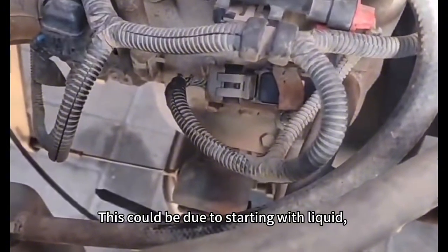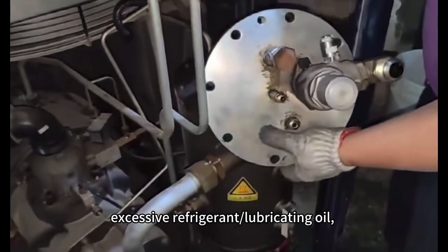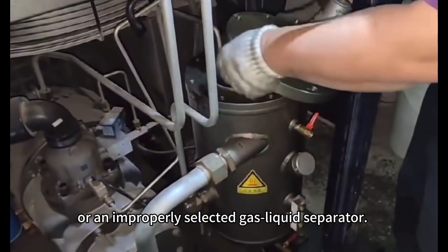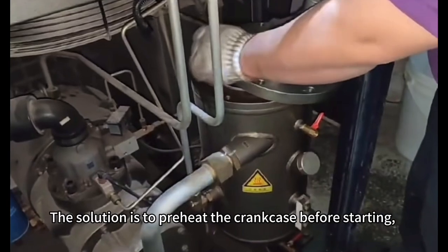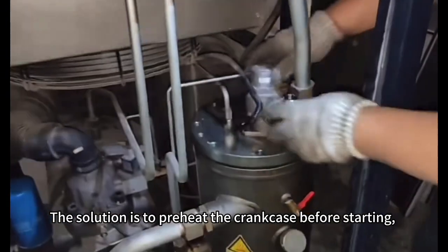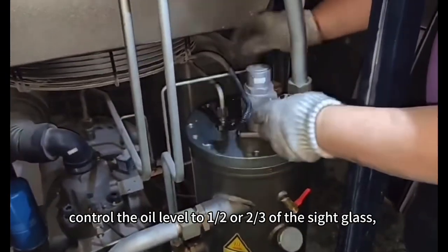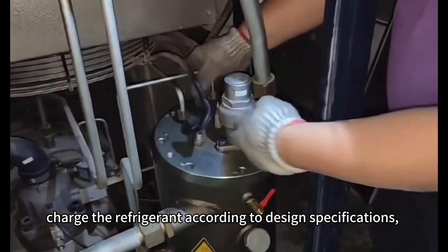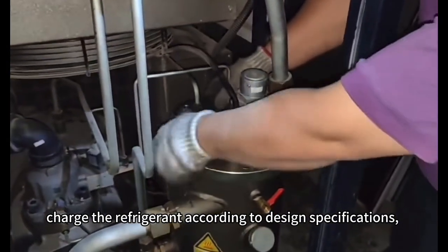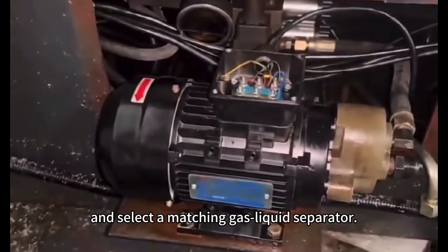This could be due to starting with liquid, excessive refrigerant or lubricating oil, or an improperly selected gas-liquid separator. The solution is to preheat the crankcase before starting. Control the oil level to a half or 2/3 of the sight glass. Charge the refrigerant according to design specifications, and select a matching gas-liquid separator.